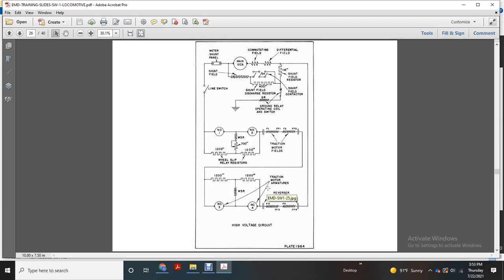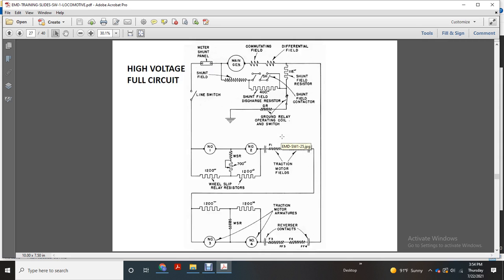Alright, high voltage cabinet. Starting at the bottom, you have reverse contactor traction motors, 1200 ohms, wheel slip relays, wheel slip relay resistors, number 1 and number 2 traction motor fields, a ground to the ground relay operating coil switch, and shunt field contactor, shunt field discharge resistor, shunt field resistor, differential field, the commutating field, main generator, shunt field, meter shunt panel, and the shunt field goes to the line switch, goes to the traction motor. That's a high voltage circuit.